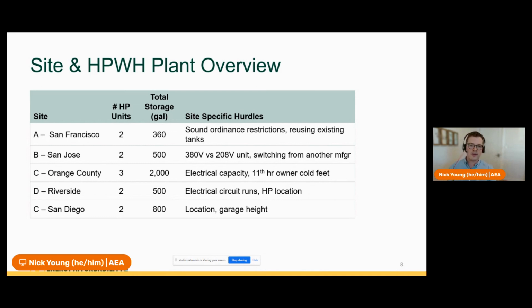Our other projects have faced issues with electrical capacity. That's why our Orange County project has such a high ratio of storage to heat pump, because they're really limited on the electrical capacity side. A standard design really would have had 4 heat pumps for that project, but they were only able to fit 3 within the electrical constraints.